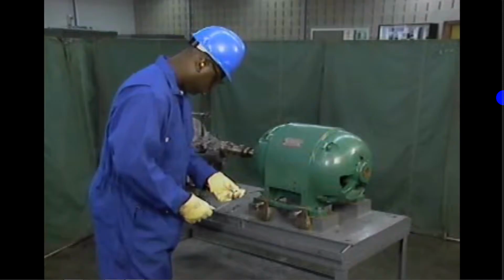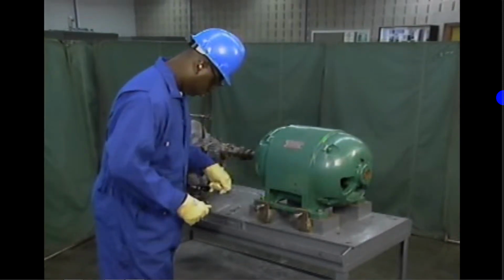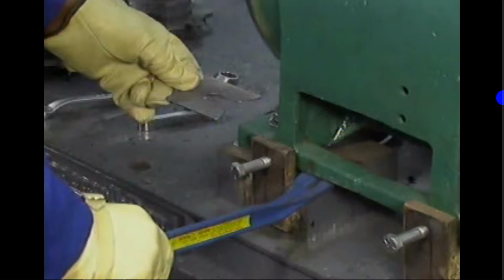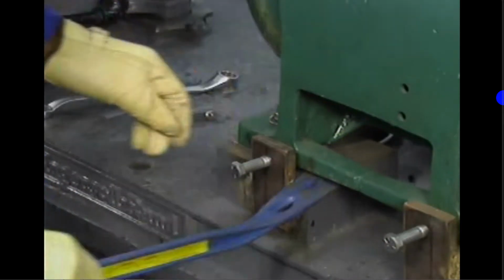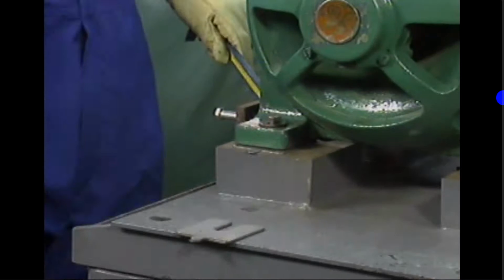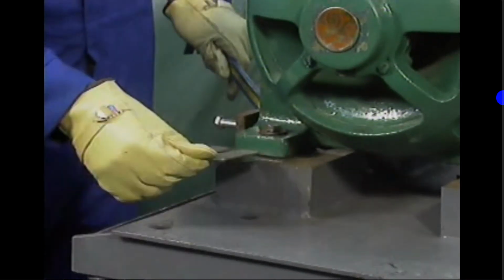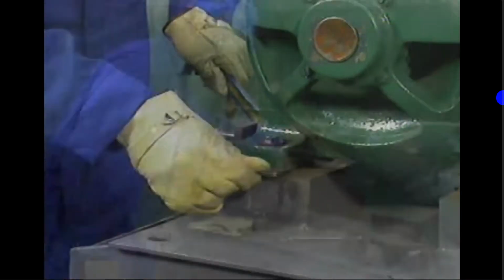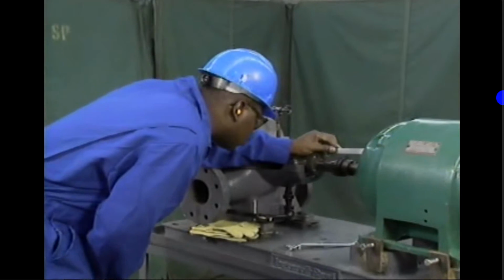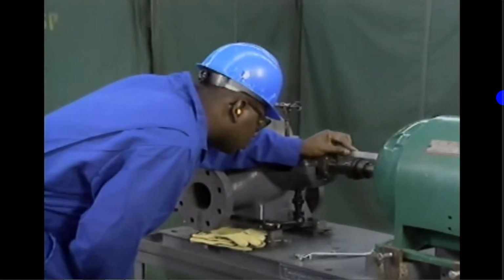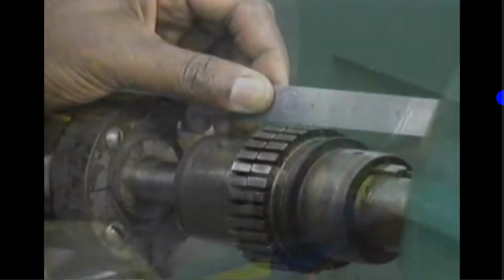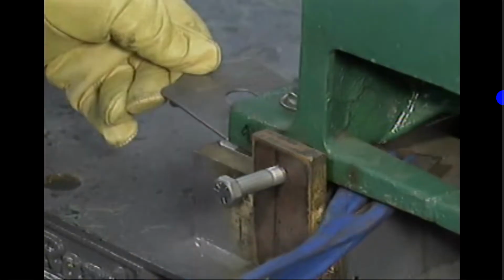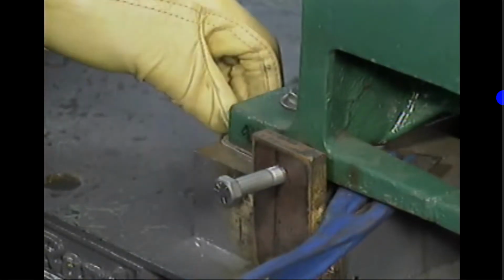So the mechanic loosens the hold-down bolts on the motor's mounting feet and adds what he thinks are enough shims to correct the misalignment. Because of the angular misalignment, he shims to raise the back end of the motor more than the coupling end. Then he repeats the measurements to make sure that the shims took care of the problem. If there's still misalignment in the vertical plane, he'll continue adjusting the shim thicknesses and measuring as needed until the shafts are close to being aligned.